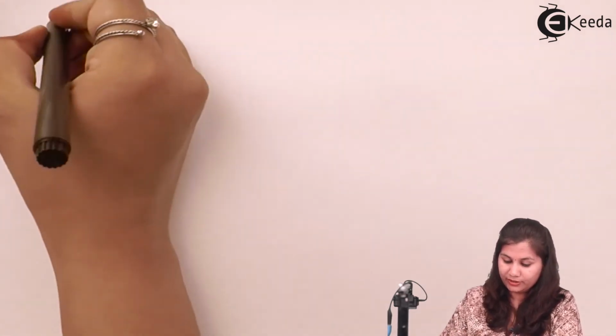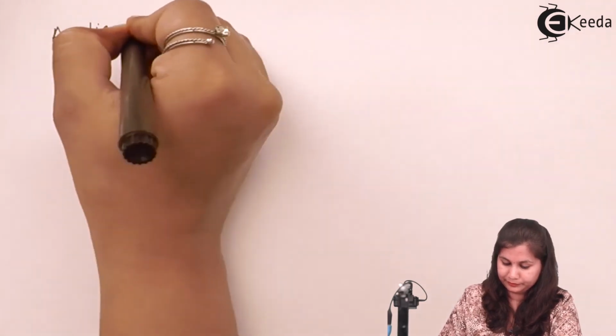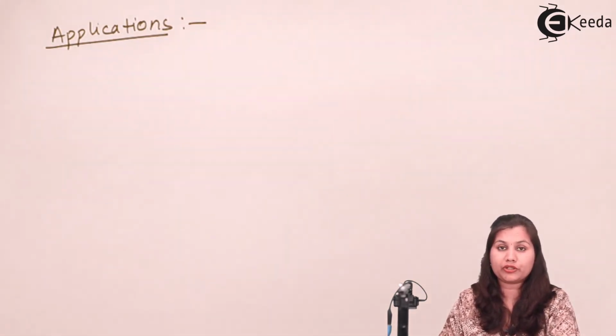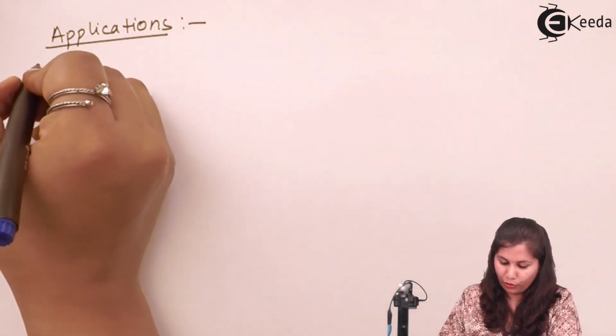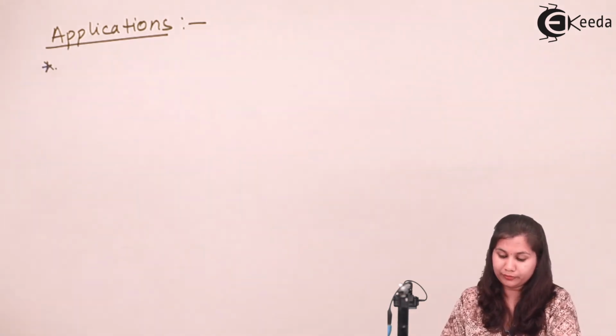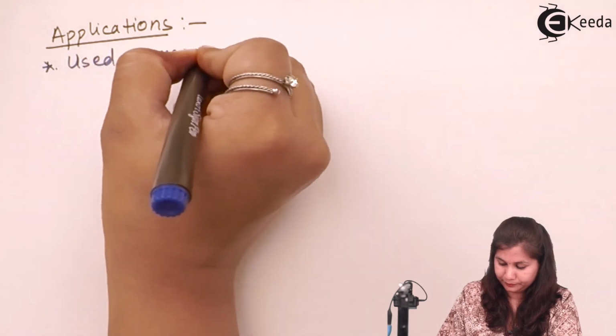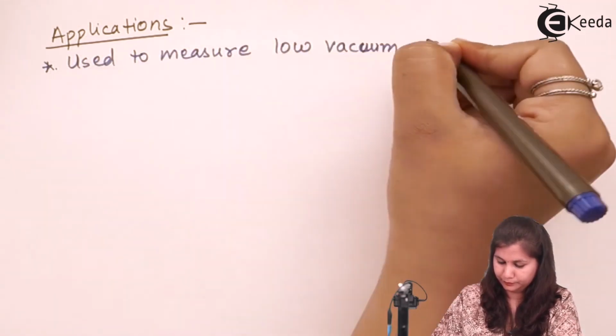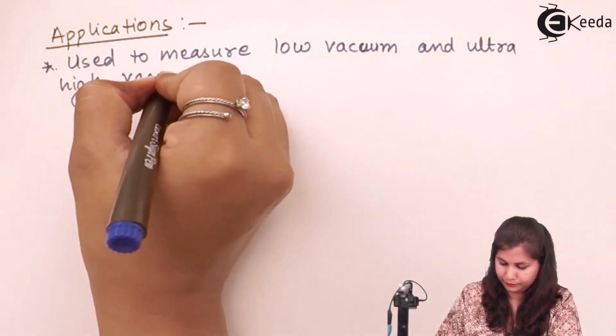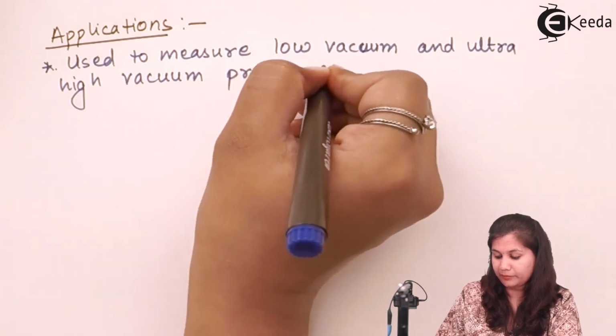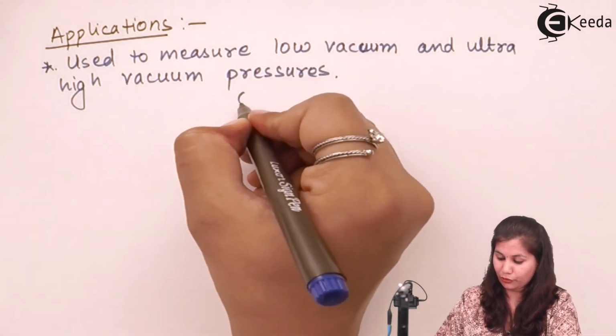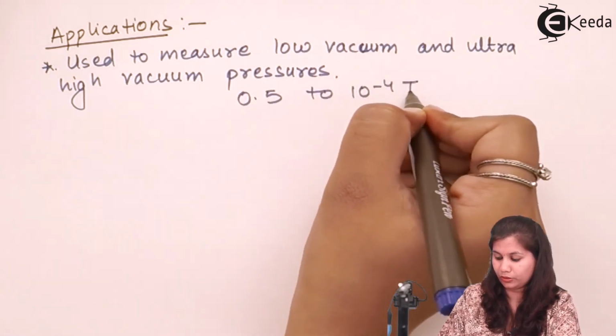Now let's come to the applications. As I have told earlier, the Pirani gauges are used for the measurement of low pressures like the vacuum, and also the pressures in the range from 0.5 torr to 10 raised to the power minus 4 torr. So we can say that they are used for the measurement of low vacuum and ultra high vacuum pressures. So generally the vacuum pressures in the range from 0.5 to 10 raised to the power minus 4 torr are measured by the Pirani gauges.